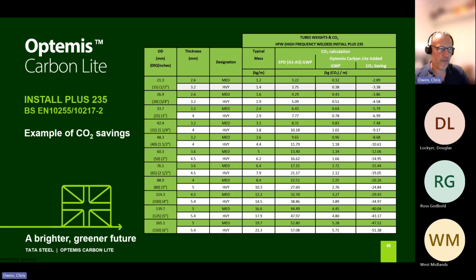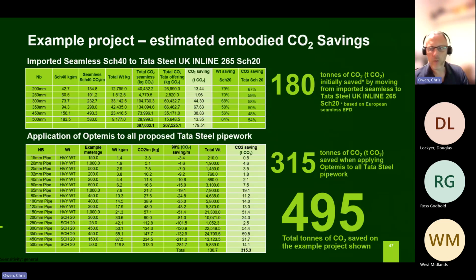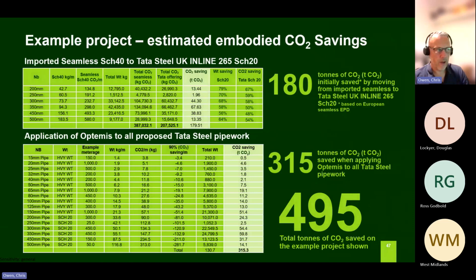When I gave the first CPD we had a rough example, but since then we've had a project in London taking the Optemis tube. We worked with the specifiers and consultants and were able to convert the initial large diameter pipework from imported schedule 40 seamless to UK welded schedule 20. The higher grade of steel meant we could satisfy the service life and pressure integrity, and that technical conversion alone saved 180 tons of CO2.